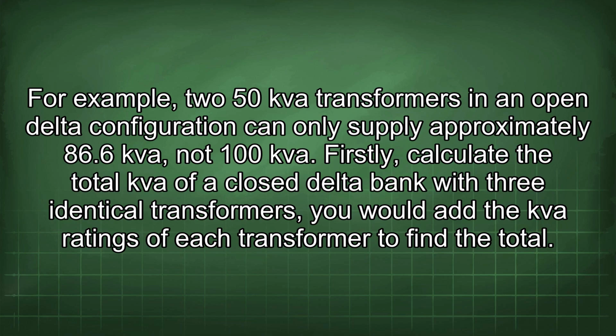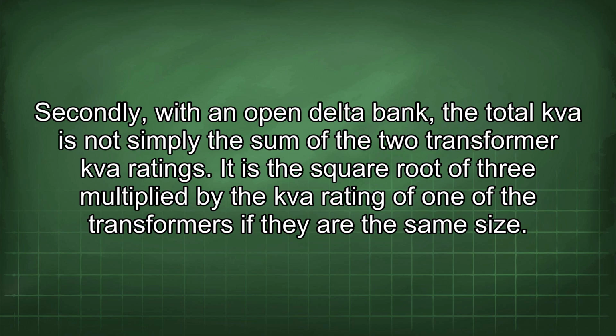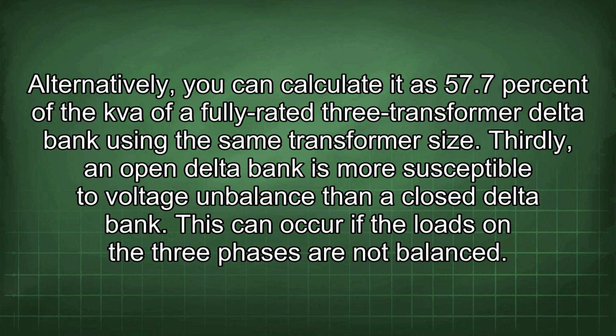Firstly, calculate the total kVA of a closed delta bank with 3 identical transformers. You would add the kVA ratings of each transformer to find the total. Secondly, with an open delta bank, the total kVA is not simply the sum of the 2 transformer kVA ratings. It is the square root of 3 multiplied by the kVA rating of one of the transformers if they are the same size. Alternatively, you can calculate it as 57.7% of the kVA of a fully rated 3 transformer delta bank using the same transformer size.